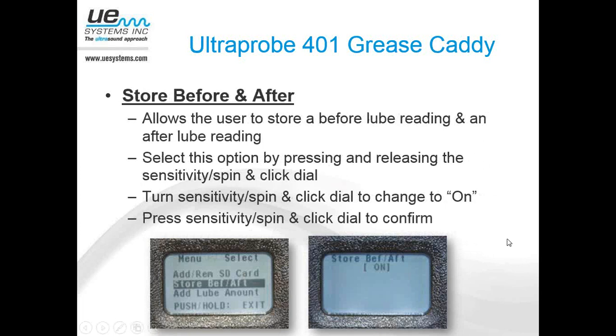So then, storing the before and after reading, and again, this is probably going to be important to you if you've got a point that's, say, currently in the lubrication alarm or the low level alarm. If you want to take a before reading and then an after lube reading, this would be how you would do that. In the setup menu, this has got to be turned on in order for you to do that. So you can see here store before and after, and then you would just select on, and that's what's going to allow you to take that before lube reading and then the after lube reading.